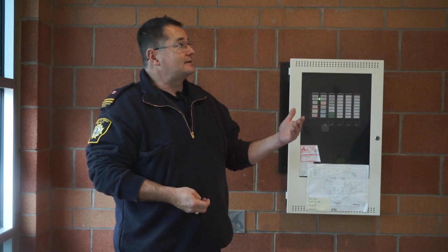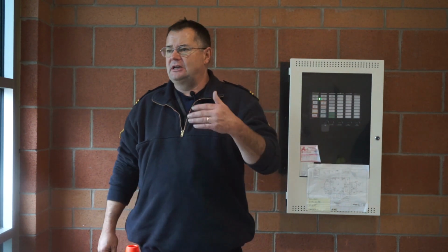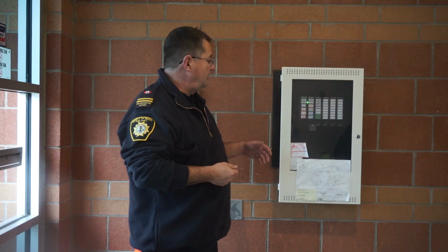So this building is classed as an assembly. It's actually a public school, and this is in the same classification as a meeting hall. Part of the assembly occupancy when we do our inspection is we need to have a look and check their fire alarm system. Now, fire alarms are required in occupancies depending on the use of that occupancy. So if you have a building that holds 300 people and you want to have 301, then that building requires a fire alarm. If you have an occupancy where alcoholic beverages are sold, then as soon as we breach 149 people in that occupancy, say a larger restaurant or a hall, we need to have a fire alarm installed.